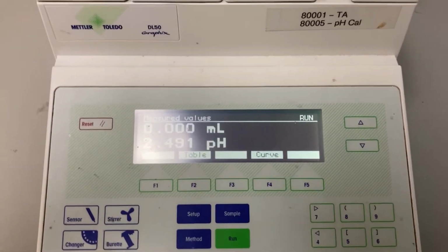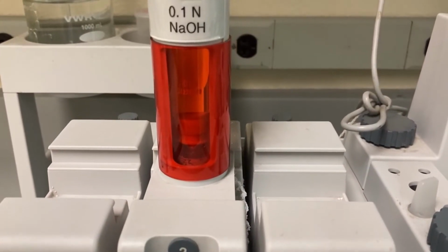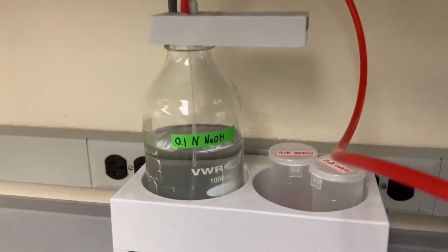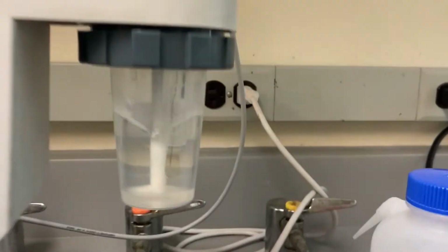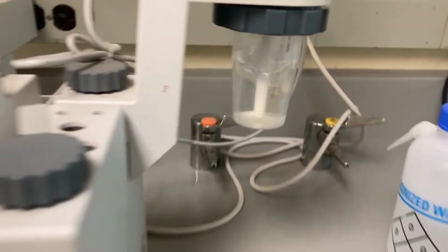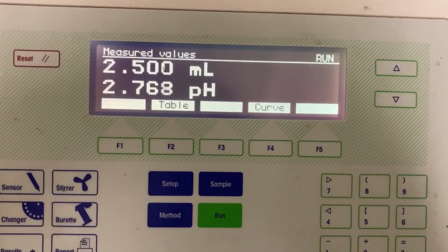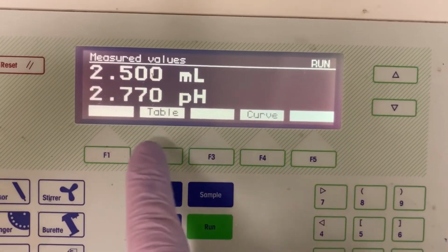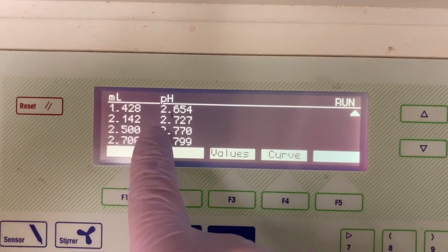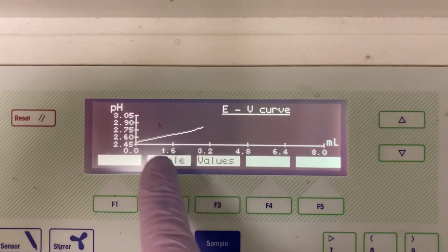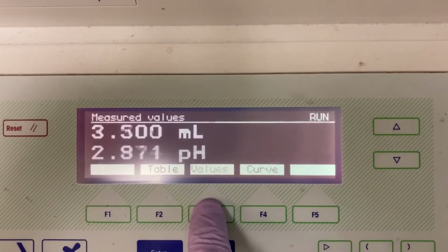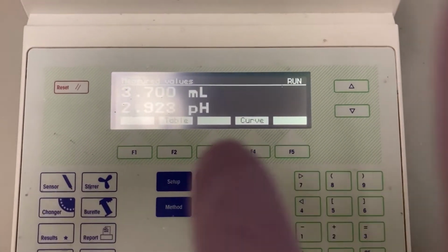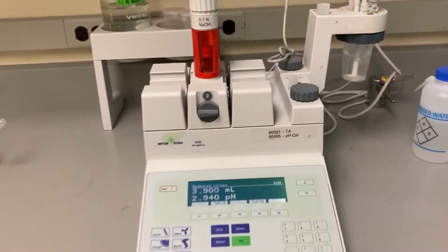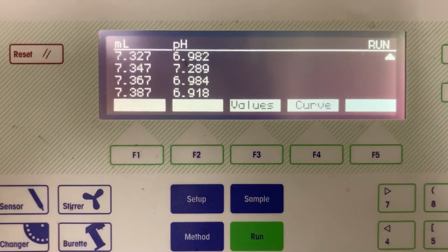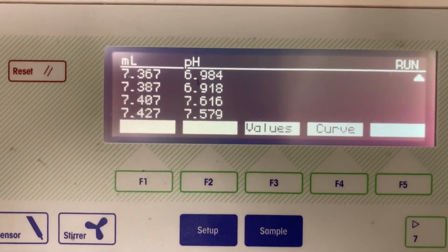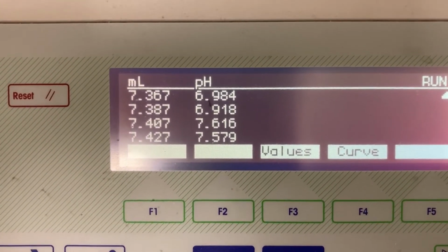So the titration has started. There is this pipette that is pulling sodium hydroxide from this storage container and pressing it into the sample cup. And as it does this, it will tell you how many milliliters it has used and the current pH of the sample. You can go to table and it will show you a history, or you can go to curve and it will show you the titration curve. Depending on the TA, the time will vary. The higher the TA, the longer the titration will take, and the less the TA, the shorter it will take. The titration will end when the pH reaches about 8.2 pH.